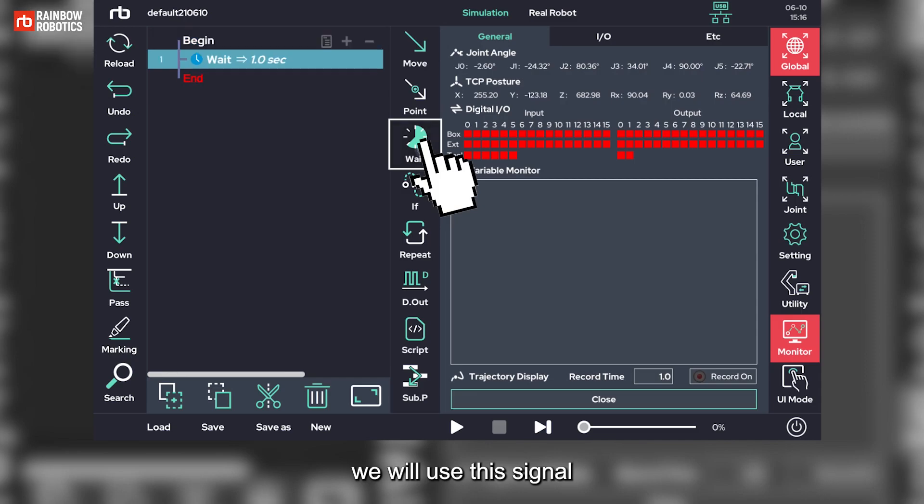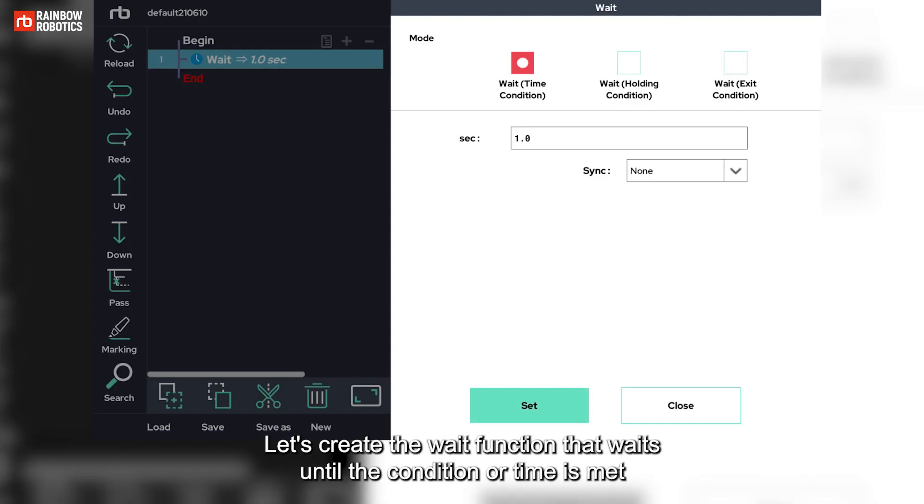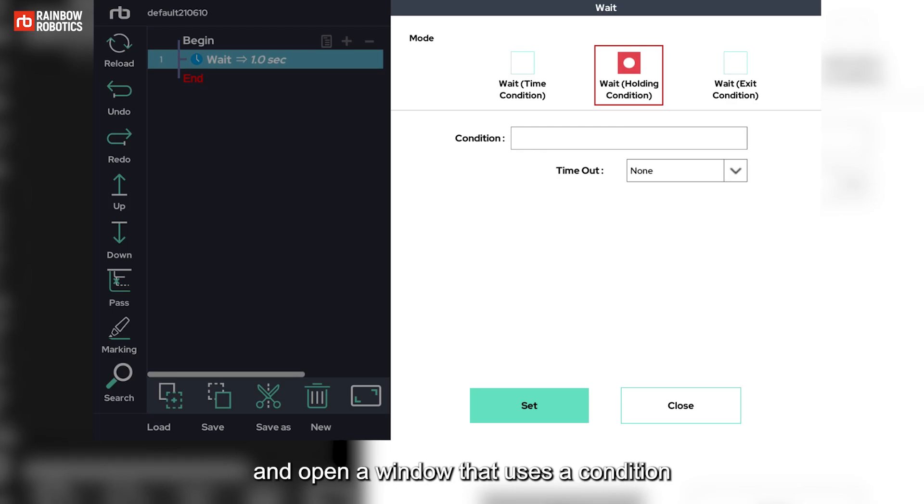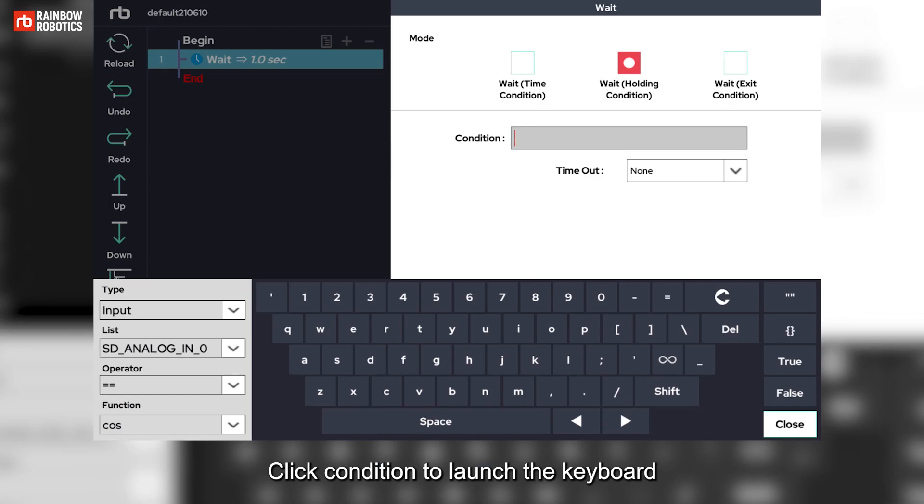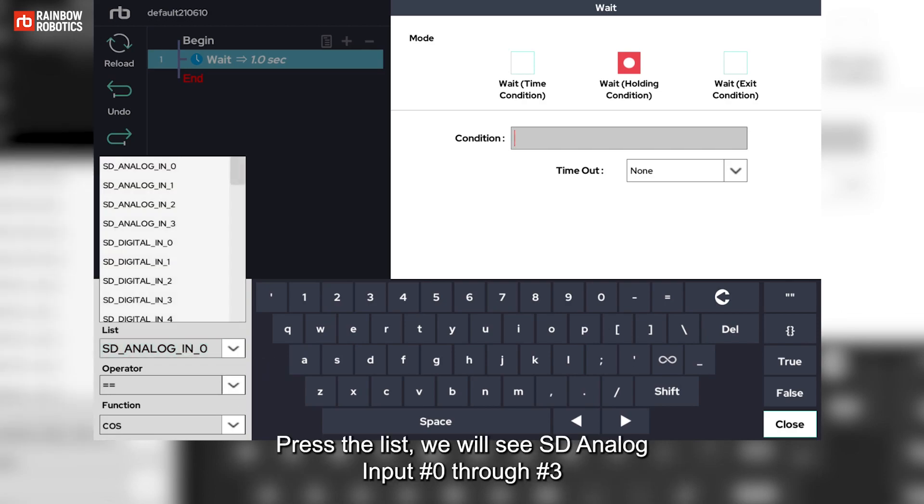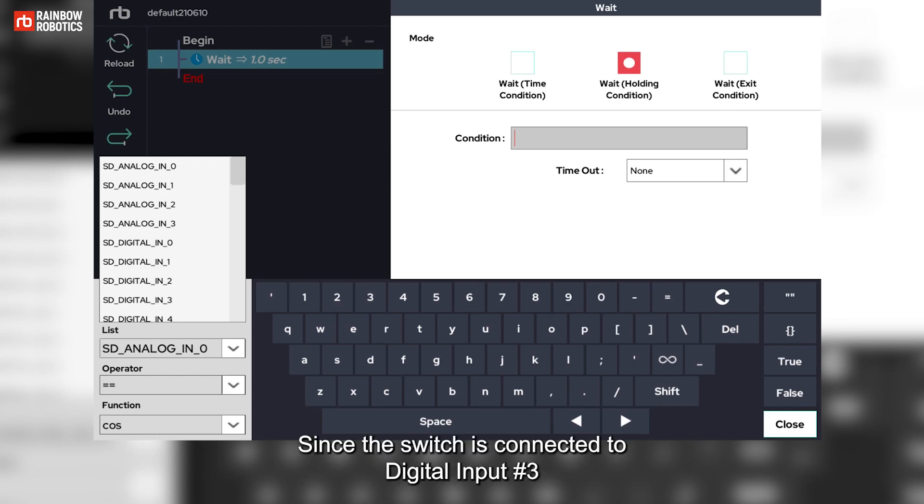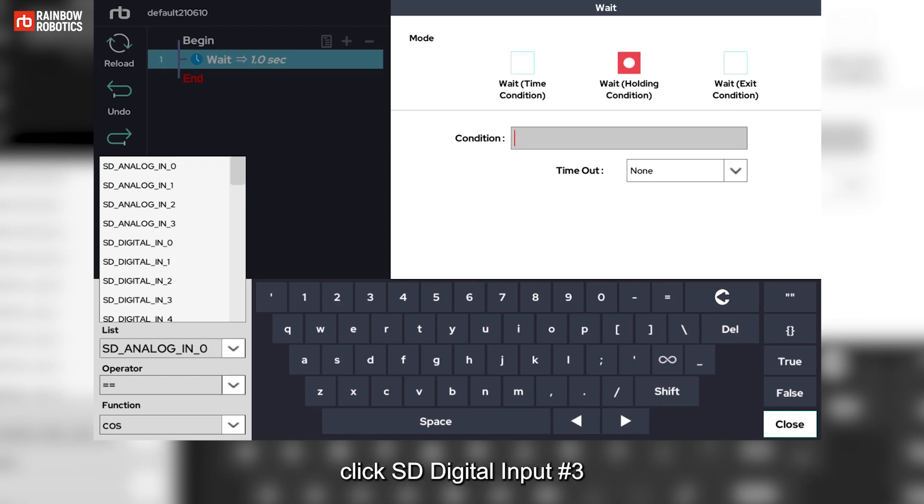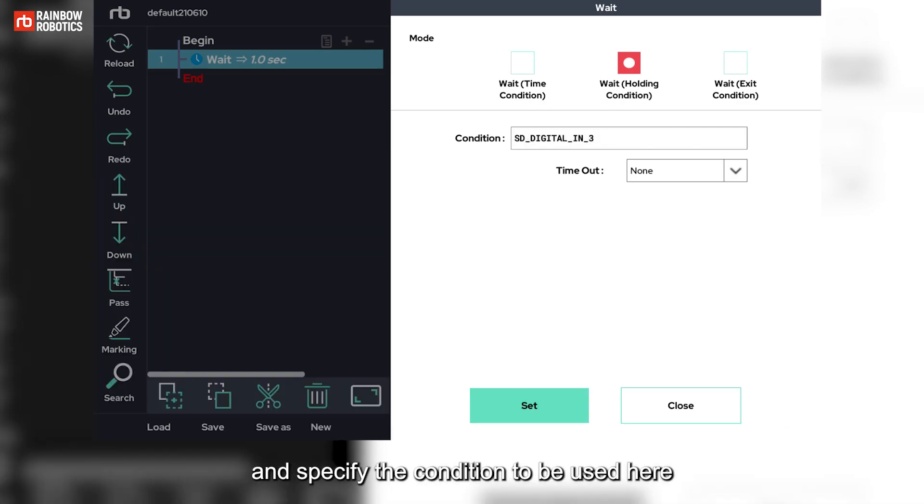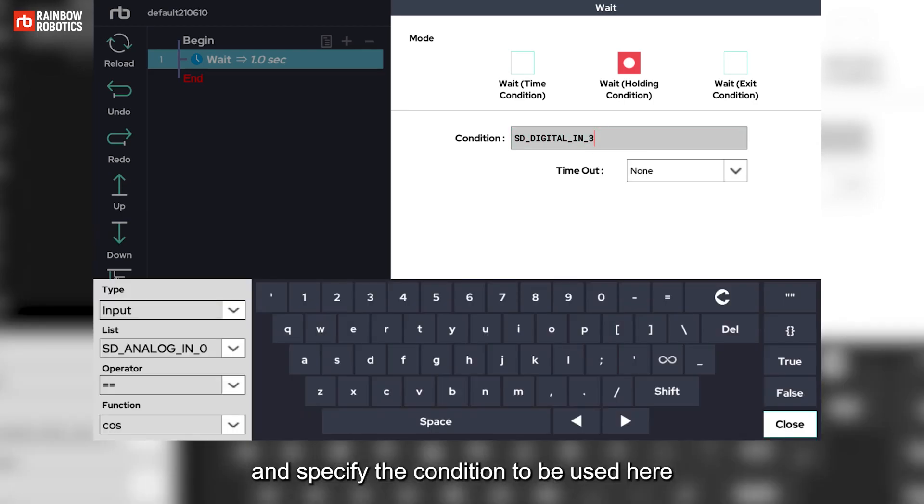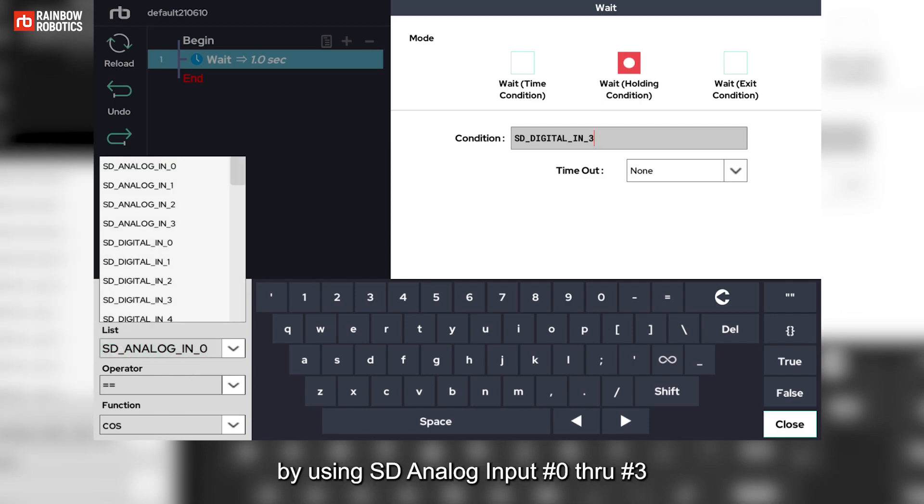Let's create the wait function that waits until the condition or time is met and open a window that uses a condition. Click condition to launch the keyboard. Set the type on the left of keyboard to input. Press the list, we will see SD analog input number 0 through number 3 and SD digital input number 0 through number 15. Since the switch is connected to digital input number 3, click SD digital input number 3 and specify the condition to be used here. In this way, specify conditions by using SD analog input number 0 through number 3.